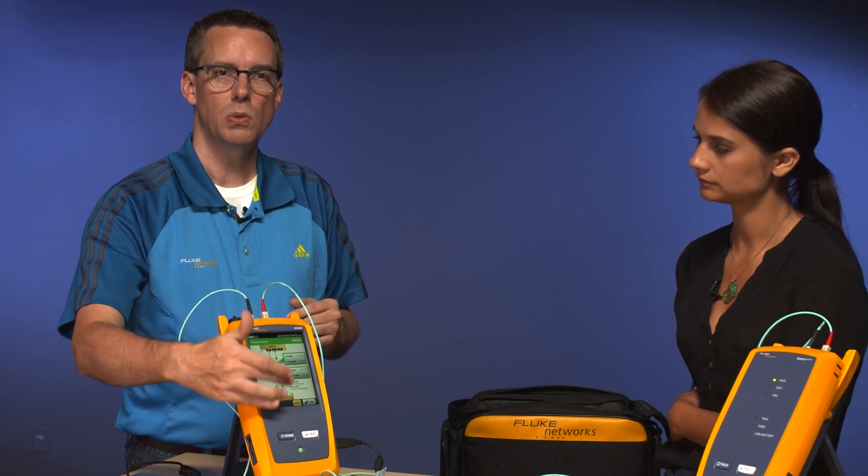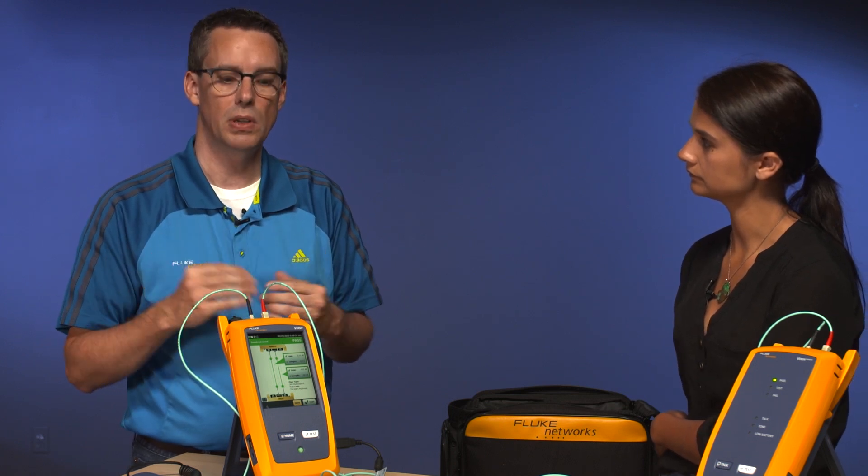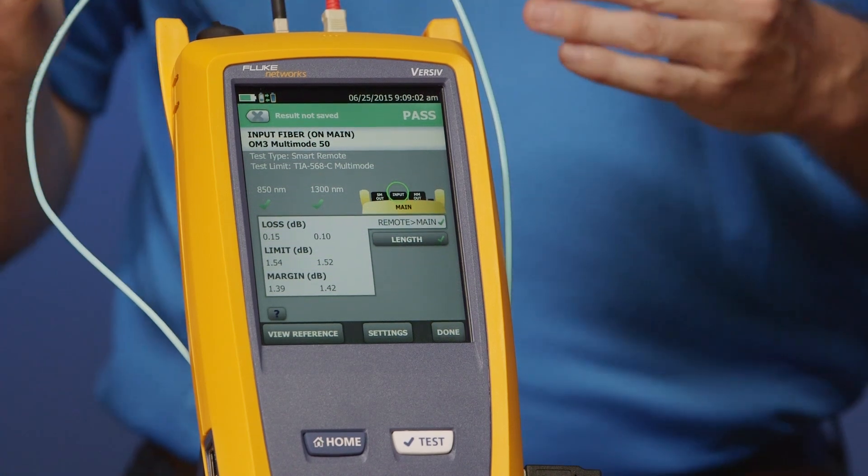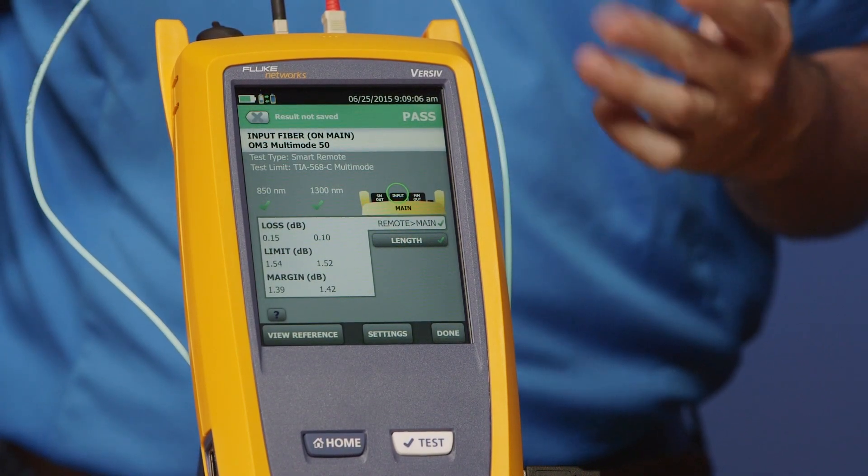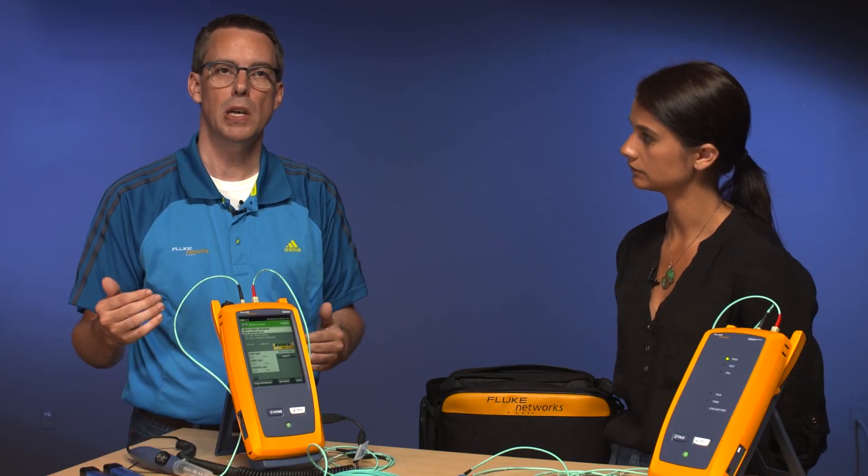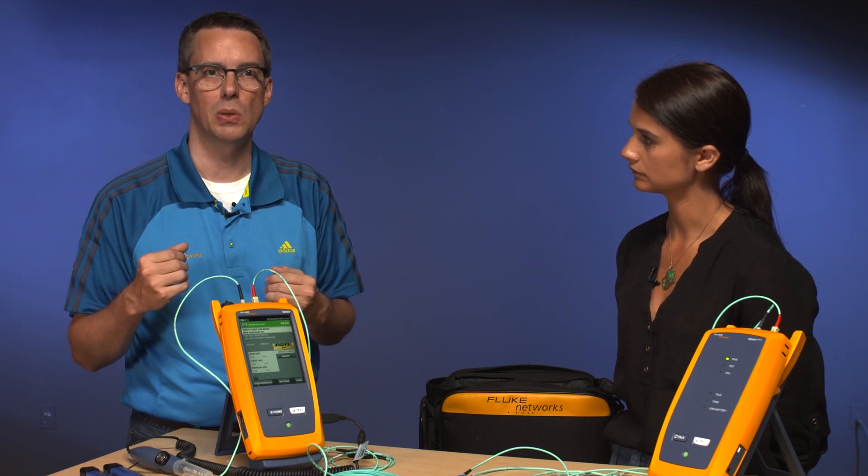You'll also notice we've got our green boxes here. That's indicating our loss, and it's pointing to which fiber it's referring to. Go ahead and hit one of those green boxes for me. So you can, if you want to, drill into detail, and in here you'll see what the loss actually was at both wavelengths, and the limit that was calculated based on the length of the fiber measured and how many connectors that you put in the tester, along with that test limit that you selected.